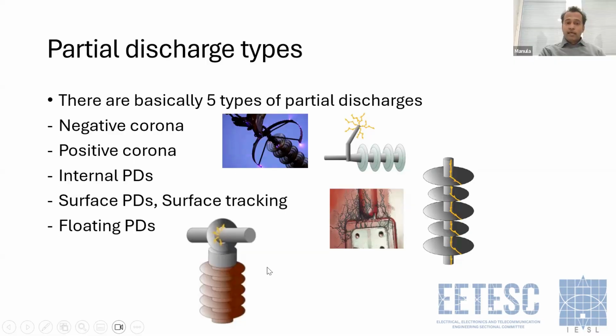But there might be other types of floating partial discharges. For example, if your earth resistance is high, and some of the metallic surfaces might have elevated floating potential, so that there might be discharges from high voltage potential to those floating potentials. That would indicate serious design failures. So those types of floating discharges always should be addressed in a timely manner.